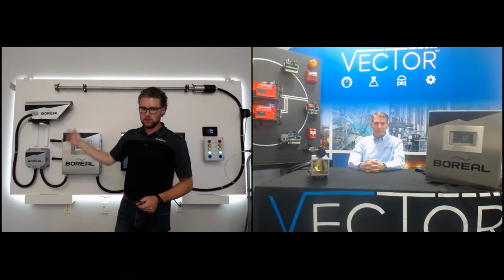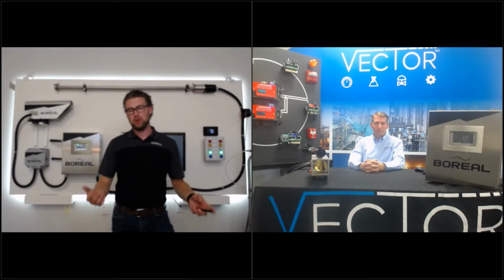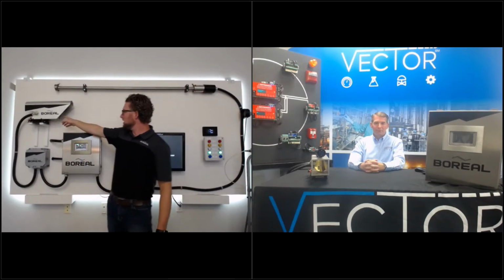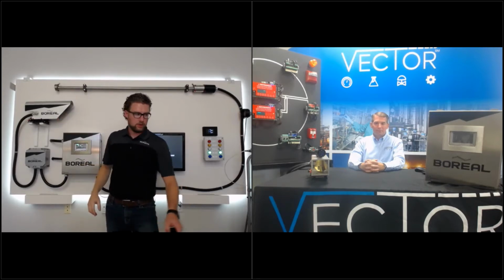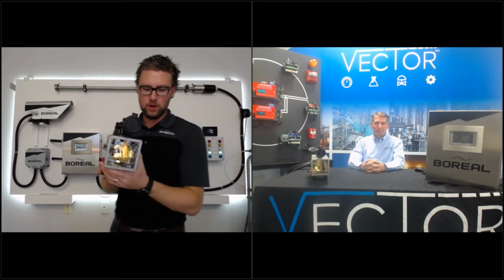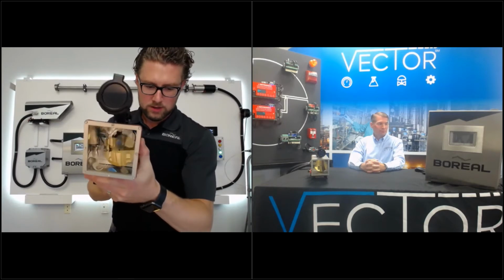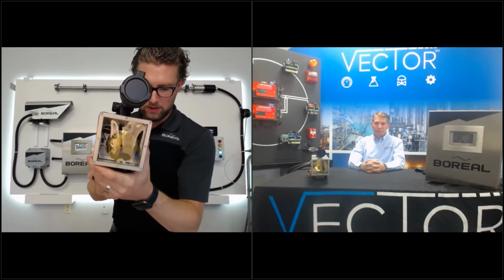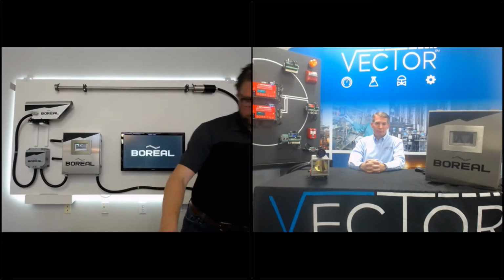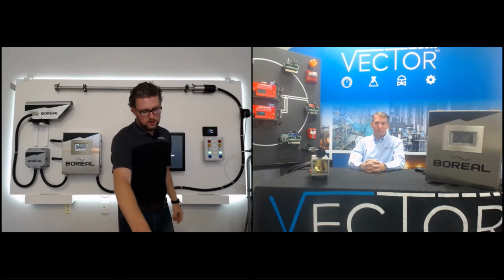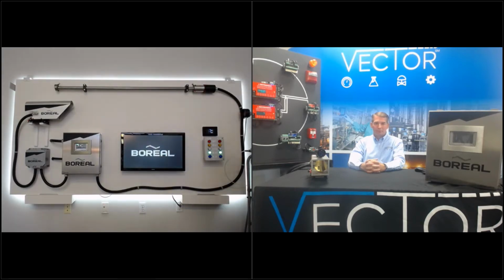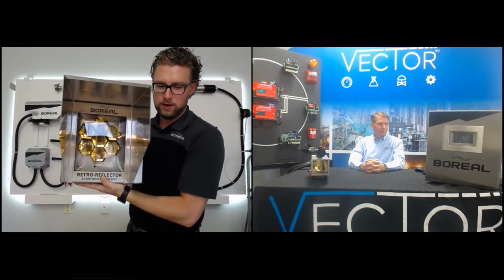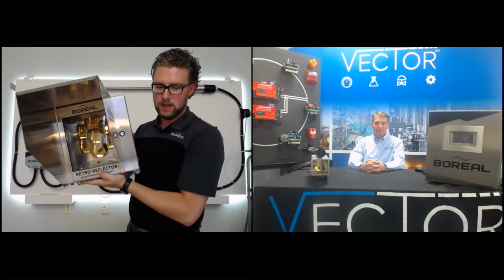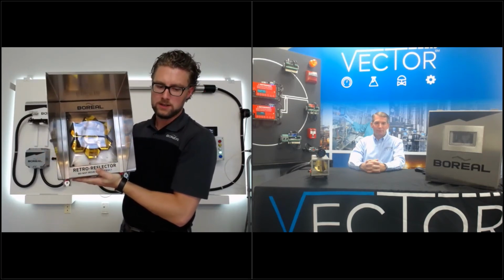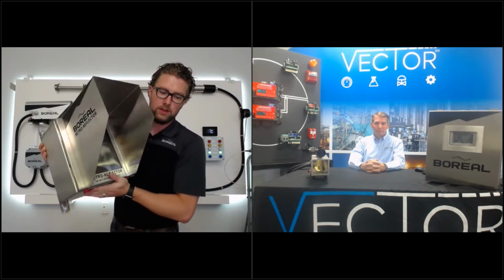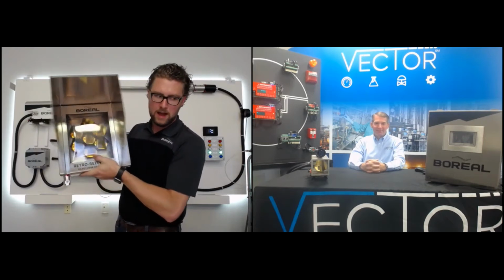To help explain what this technology does, laser-based gas detection is really a simple premise of operation. We emit laser light that shines from our transceiver. I'll show you a closer example of the OpenPath measurement head. I'll give this time to align and focus. Inside the OpenPath measurement head, you'll see a hole in the middle of that bowl-shaped mirror. The laser shoots out of that arrangement and bounces off of a retroreflector. A retroreflector is three flat plane mirrors butted right up beside each other. The laser will enter those corner cubes and be returned at the exact same angle at which it entered. So think of this as a really fancy mirror, so to speak. This is what will return the laser light back to the transceiver.